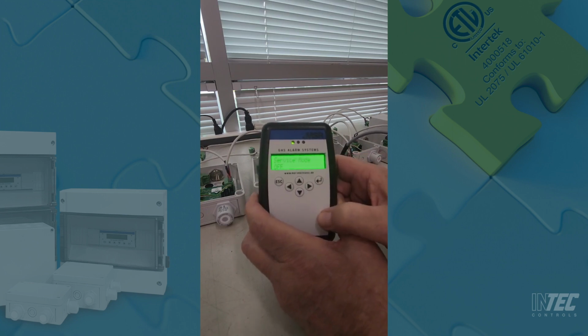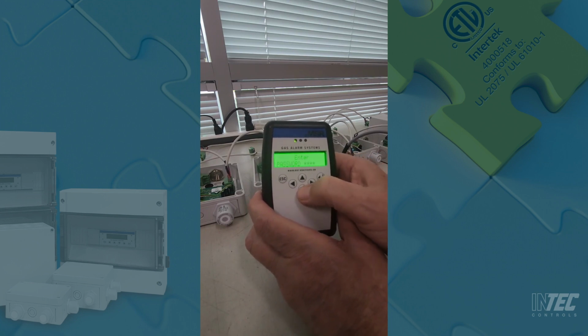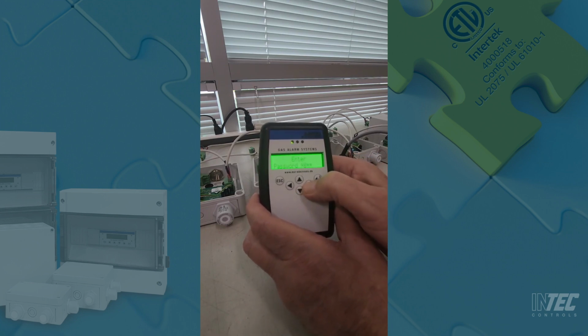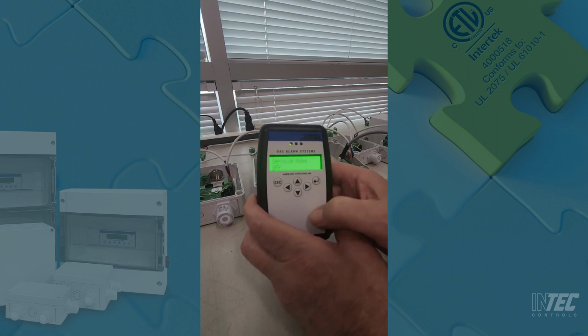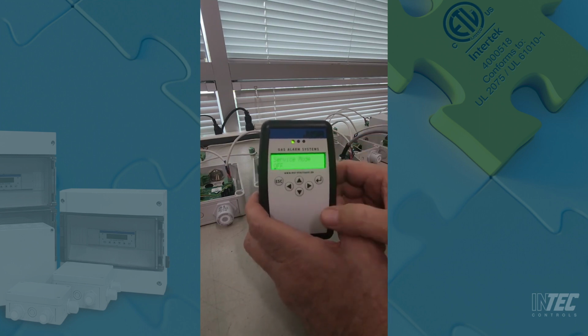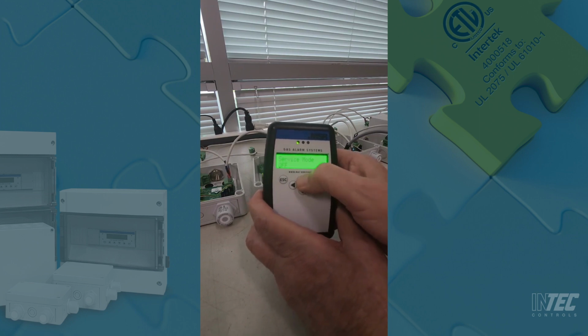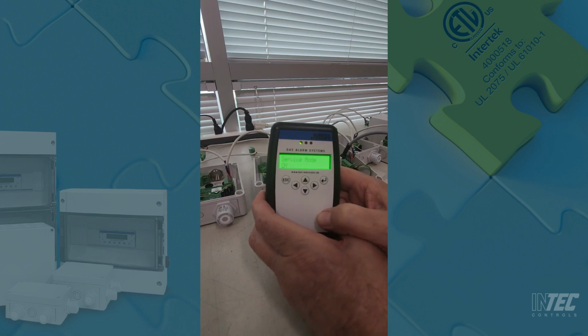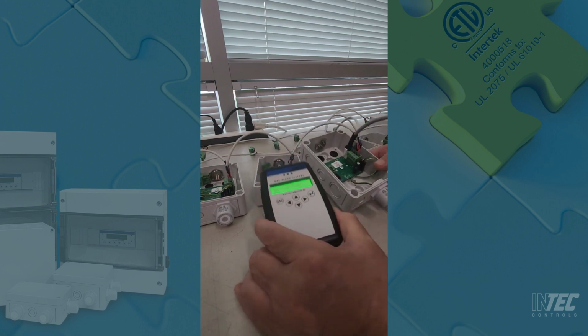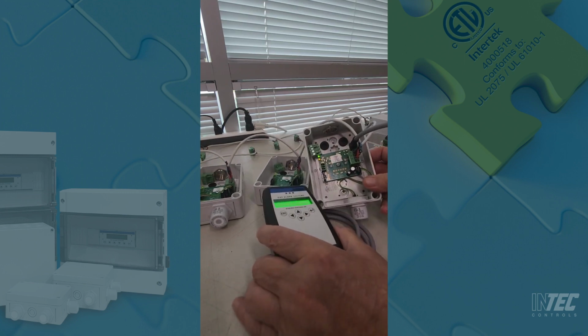It shows service mode off. We're going to hit the enter button again. It's going to ask for the password. The password is 9001, and then hit enter. Notice the little cursor under the O of off. Arrow up to turn it to on, and then hit enter to make that cursor go away. You'll notice on the sensor board how the yellow LED will be blinking when it's in service mode.